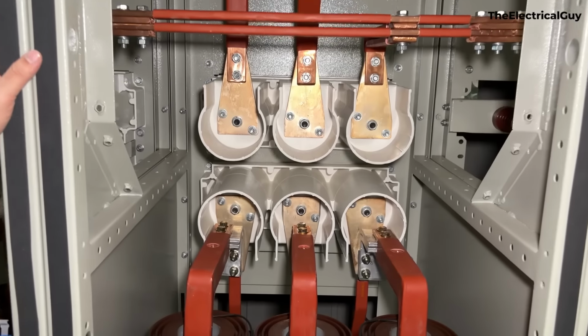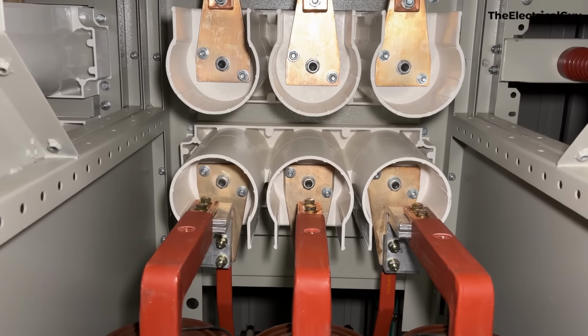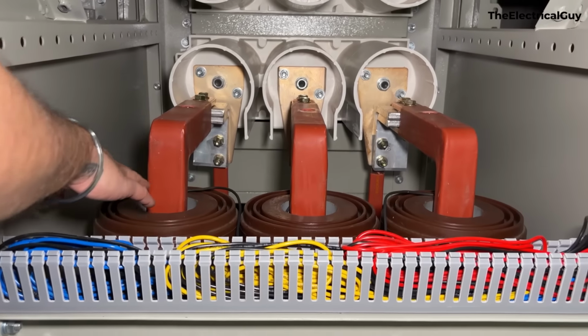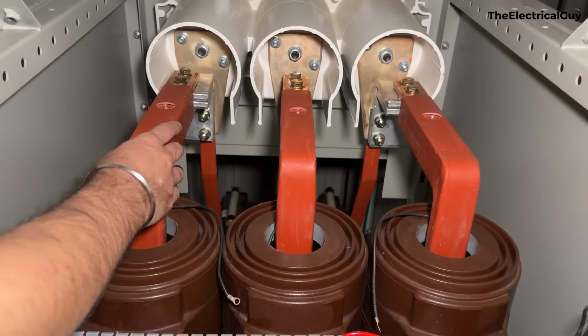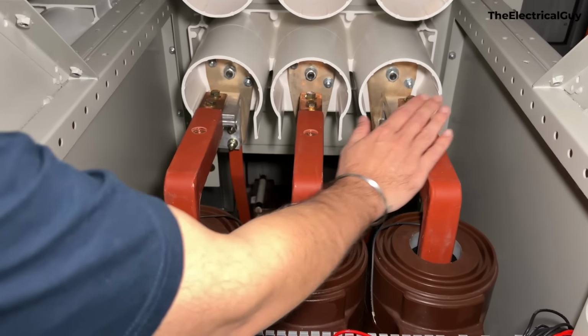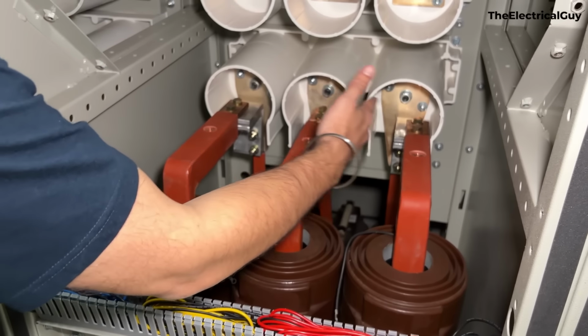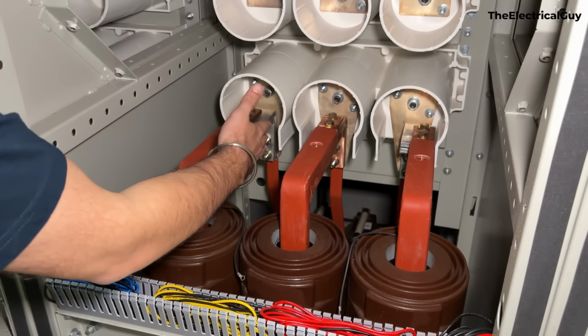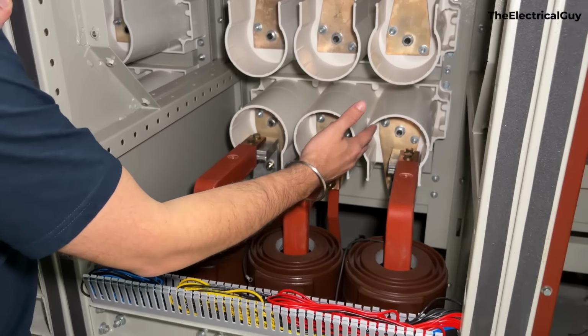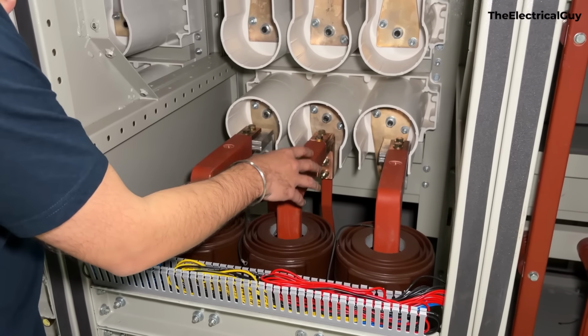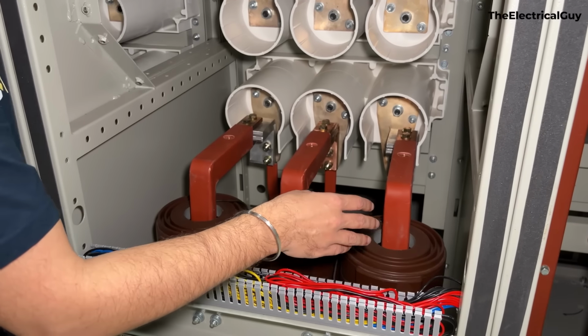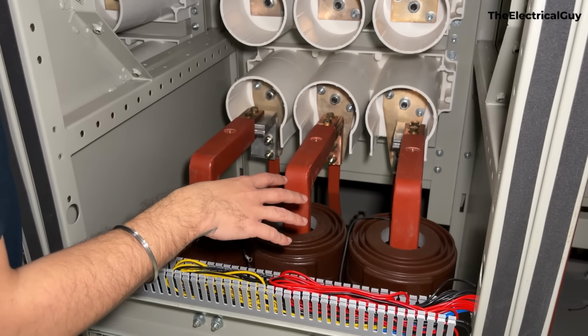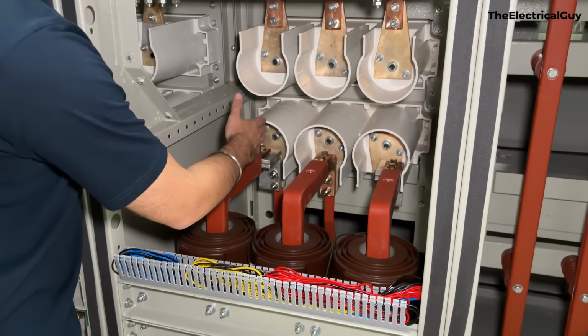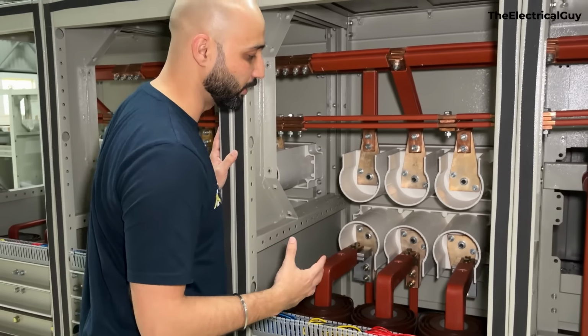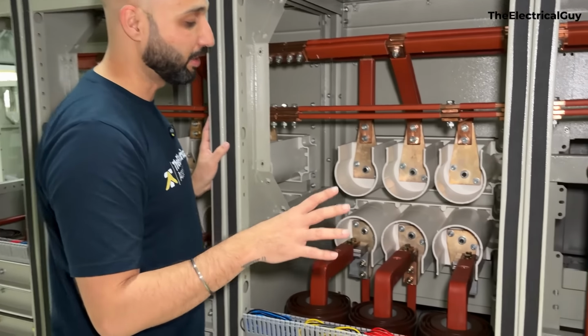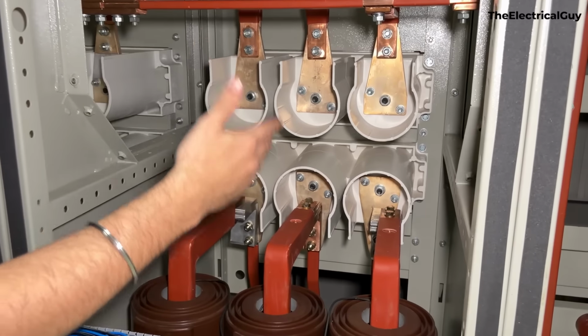So as I mentioned, this is an air insulated type of panel. Now what is the difference between air insulated and gas insulated? Let's understand that. So you see we have three phases here, R phase, Y phase and B phase. And in between these two phases, the insulation at the moment is the ambient air that we have. So that's why we call it as the air insulated switchgear. But let's say if this is a gas insulated switchgear, then we would be adding the SF6 gas or any other insulating gas to this, and that is what we call as the gas insulated switchgear.